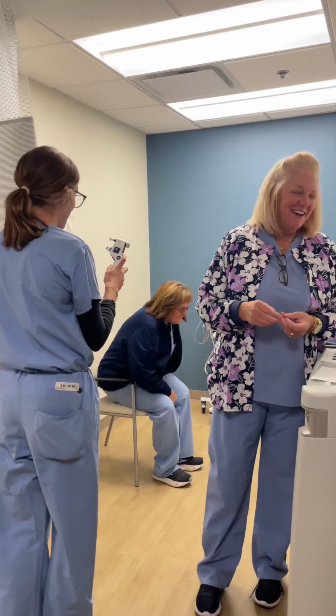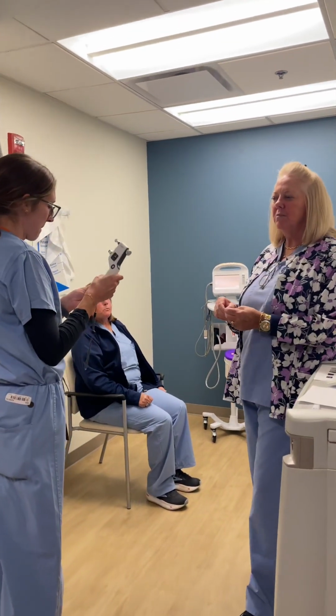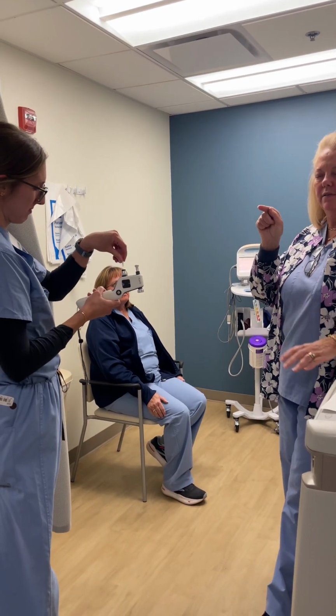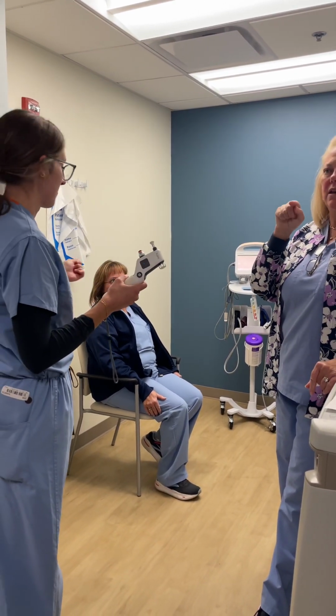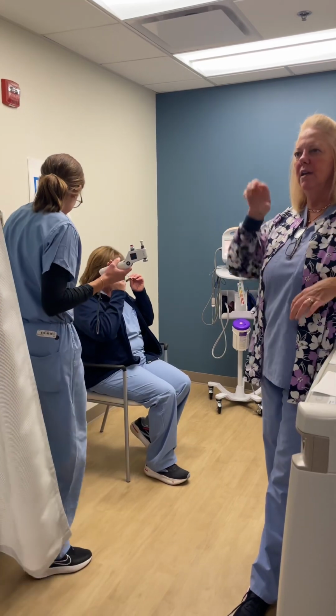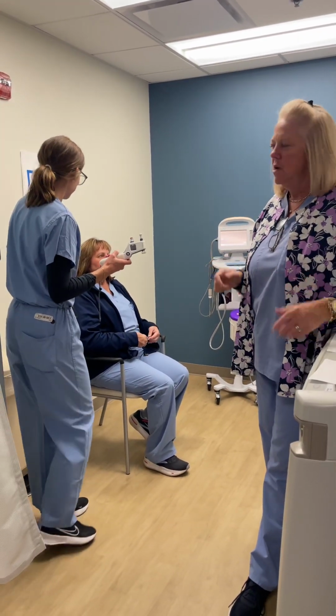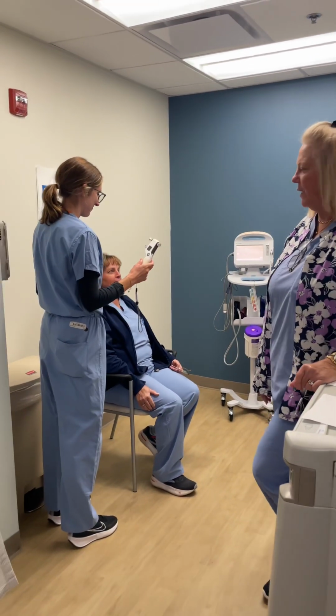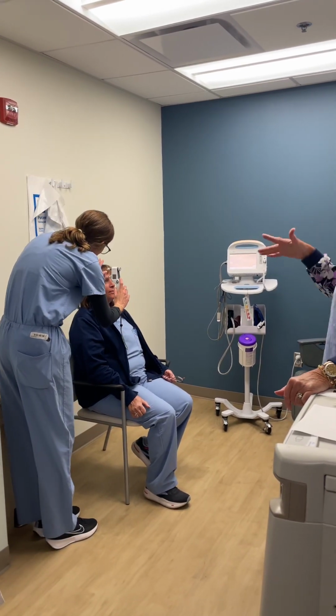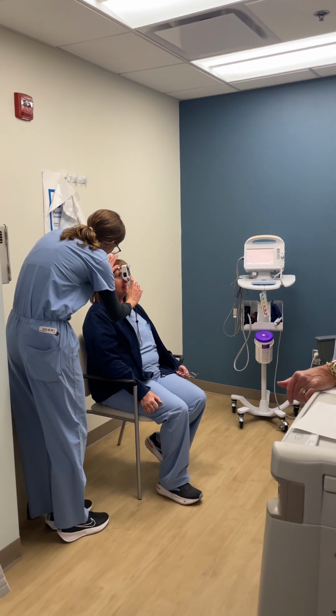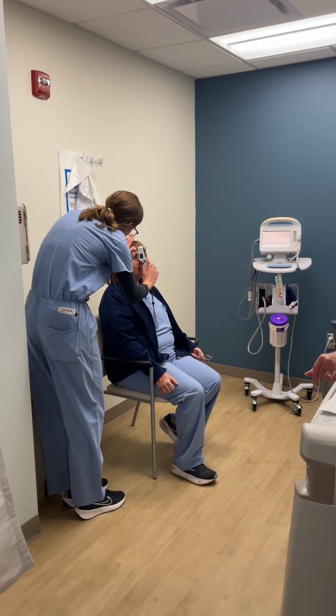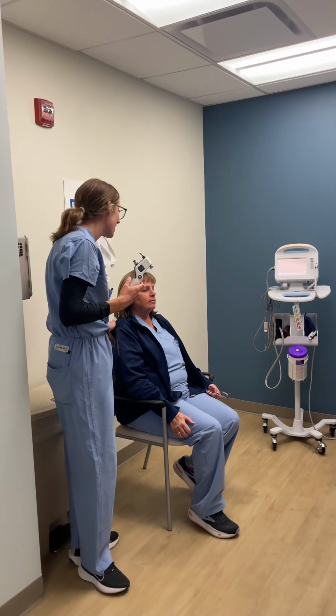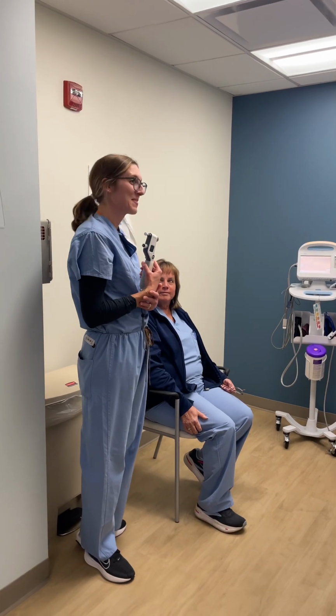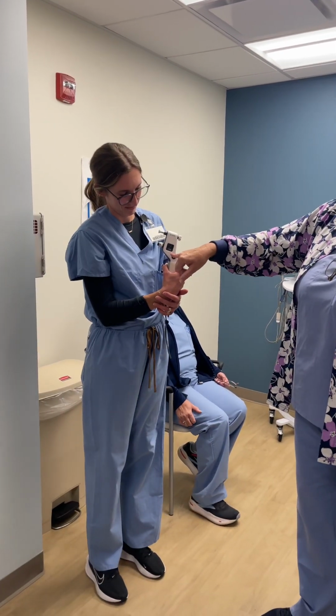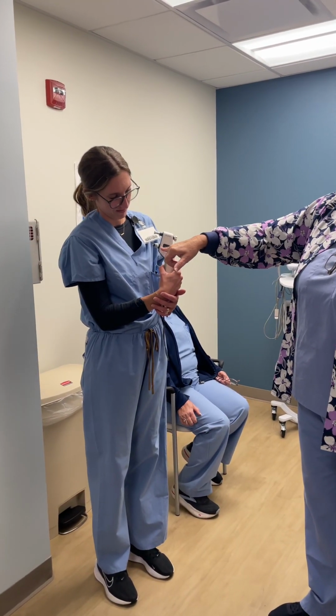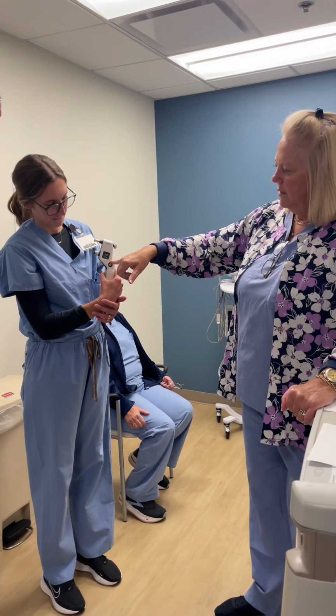There you go. So the way the machine works is it takes 6 readings in a row, and then it averages them. It actually gets rid of the highest and the lowest and averages the 4. So that's what they're considering your reading. Have the patient sit straight up and down and look straight ahead. You want to be 4 to 8 millimeters away from the patient's eyes. Very good. You can see it colored in every line, so that means it did the 6 readings. So that means you're good.